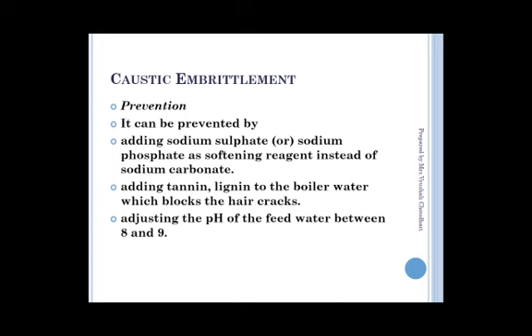It is prevented by adding sodium sulfate or sodium phosphate as a softening reagent instead of sodium carbonate, adding tannin and lignin to the boiler water which block the hair cracks, and adjusting the pH of the feed water between 8 and 9. So highly alkaline water causes caustic embrittlement. Next topic is priming and foaming.